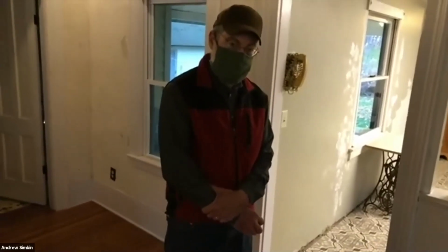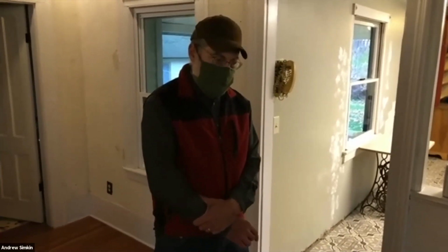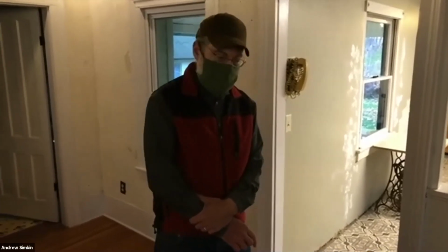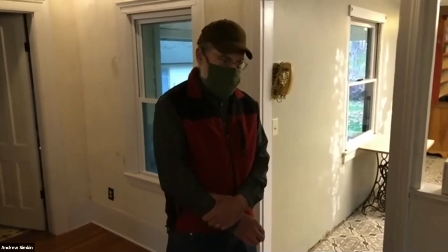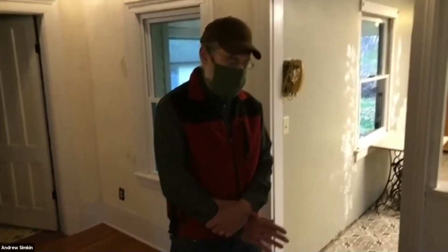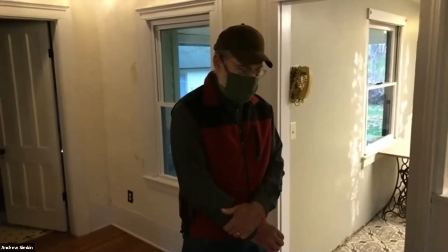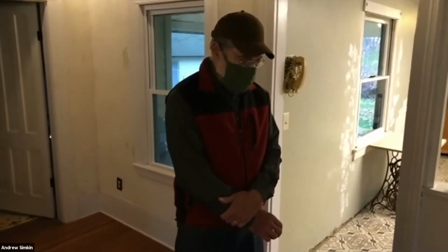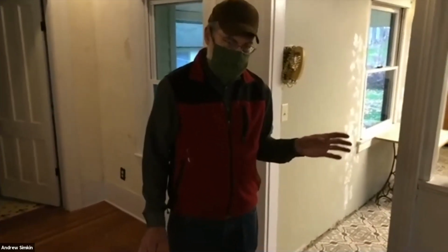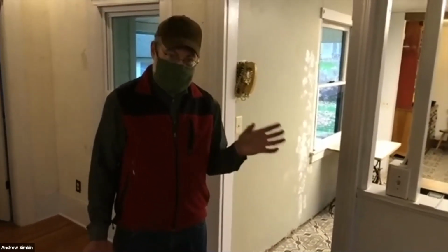How much did each of the systems cost to buy? I bought them as part of a single quote, and it came to a little over 16,000 for the whole system. And I think the rule of thumb that I had been told was that you can expect to pay roughly 5,000 per indoor head. Either the console or the wall unit would be called a head. And these wall units or consoles range from, I think the smallest is about 7,000 BTUs up to, I think the largest are about 18,000 BTUs per hour.